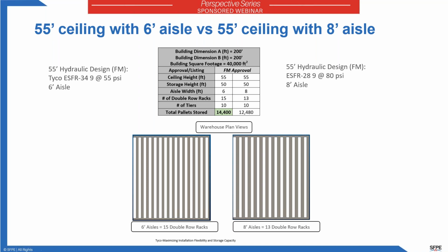The other sprinkler approved at 55 foot is approved with an 8-foot aisle. As you can see from the calculation, there's a reduction in the amount that you can store. Again, at these ceiling heights, there are certain challenges about how narrow you can make your aisles based on the commodity being stored and how that commodity is being stored in, added to and retrieved from the storage racks. But to maximize the potential for storage capacity, finding the sprinklers that are approved with a minimum aisle width will give you the most potential for maximizing the storage.